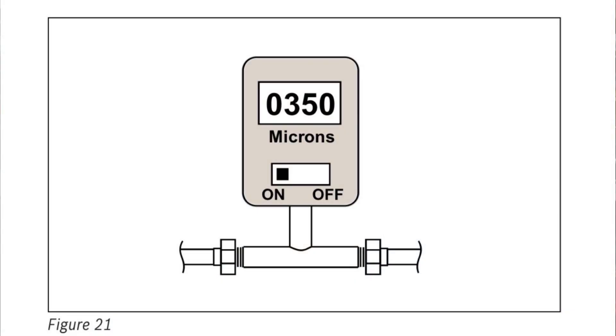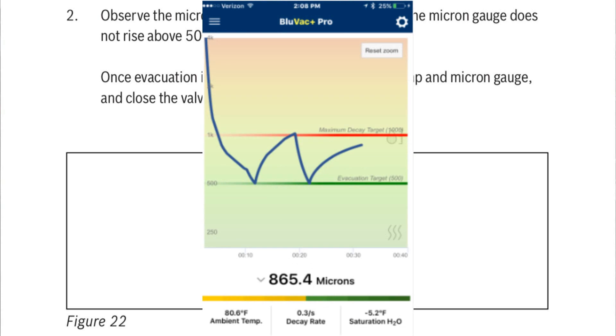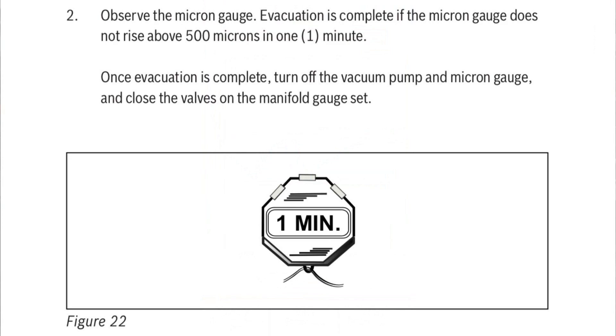350 microns is what Bosch is saying in their manual, but it's not just saying that — it says to observe the micron gauge, and evacuation is complete if the micron gauge does not rise above 500 microns in one minute. So although you're going down to 350 microns, you want to sit there for a minute and make sure that decay doesn't rise above 500 microns. If you want a more intricate look at vacuum decay, you can go to something like the BluVac app or MeasureQuick to see a graph of vacuum decay, and it gives you a prediction on whether or not your vacuum is going to be sufficient for your system.